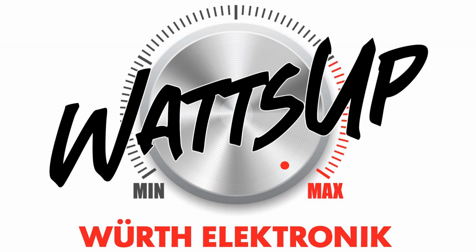How do we determine this inductance? Just by using an LCR meter, which is attached to each winding separately. And the other winding, in this case of a one-phase choke, is left open. If I would make a loop here or connect both ends of this winding additionally, then I would have a transformer principle, and I would also measure the mutual inductance, which I don't want to. So it's left open.